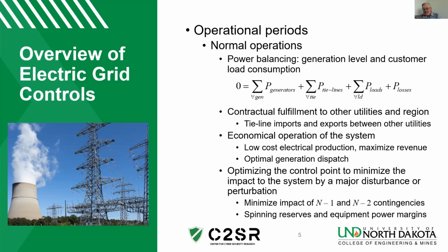Behind the scenes of what we've talked about so far, economic operation of the utility is just as important, and it folds into the controls of a power system. So optimal generation dispatch is a set of programs that run on the SCADA system, taking into effect historical data and short-term load prediction for that day and for that particular hour of the day, and trying to determine how much power generation is going to be needed, and giving the set points to generators as to which generators should be operating for the lowest possible cost of operation. And so they give input to the control systems as to the set points of our generation power output.